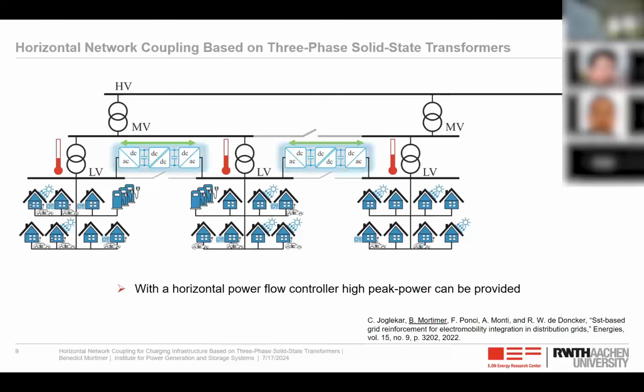Therefore, I will present today a power electronic-based load flow controller. This device, we call the solid-state transformer. And this enables us to achieve a horizontal meshing of the grid by utilizing the existing structure and cable connections that are already there. And therefore, we can provide high peak powers at certain grid connection points by just distributing the loading among the neighboring substations.